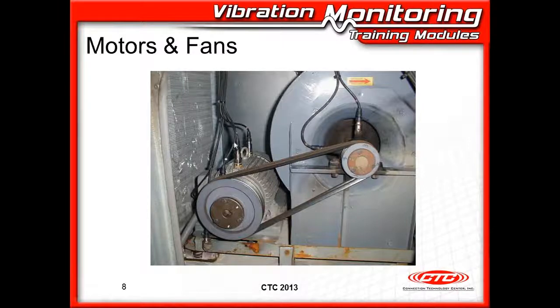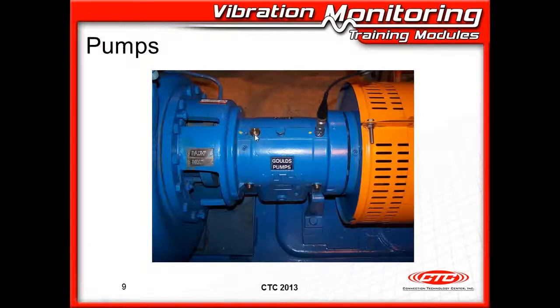We can see here that we've got accelerometers mounted on our motor. This is in the vertical direction, and also on our fan in the horizontal and in the vertical direction. This is typical of what you'd see on any motor fan unit. Here we've got a pump, and this pump actually has pre-existing mounts on it. These are quick connects, so that for a portable data acquisition system, you can simply connect to the landing target that's on the pump.